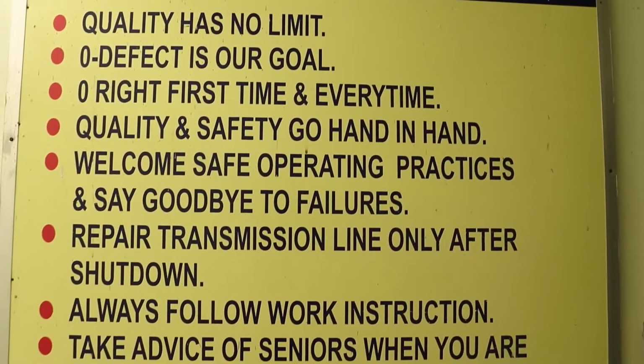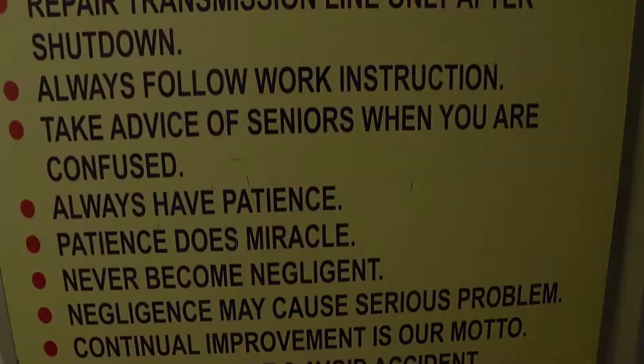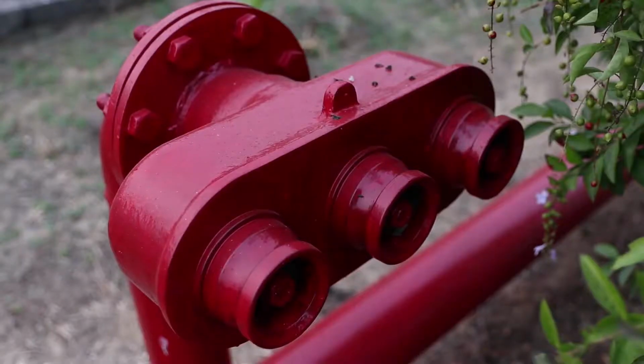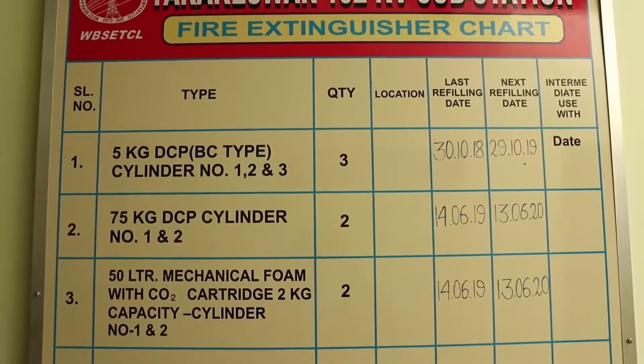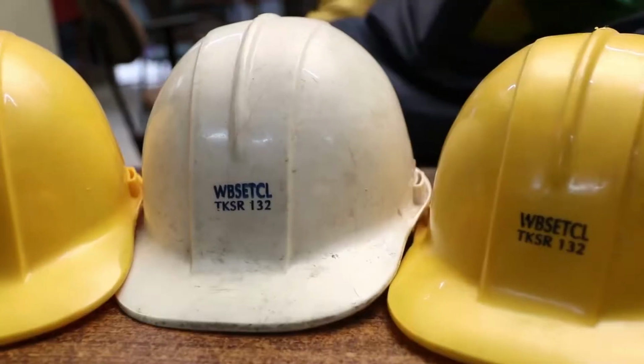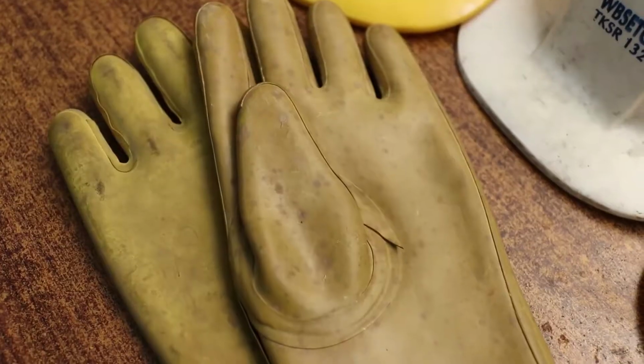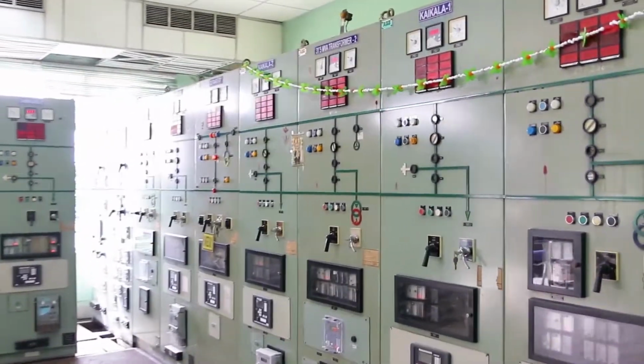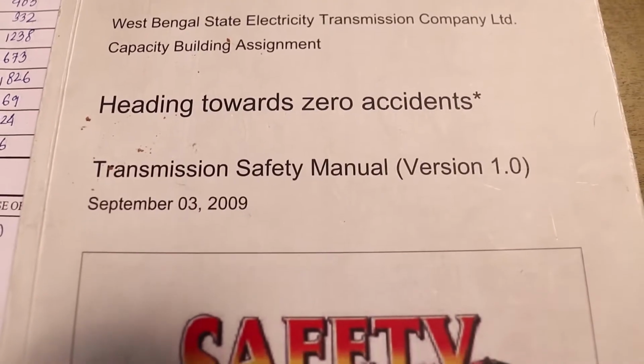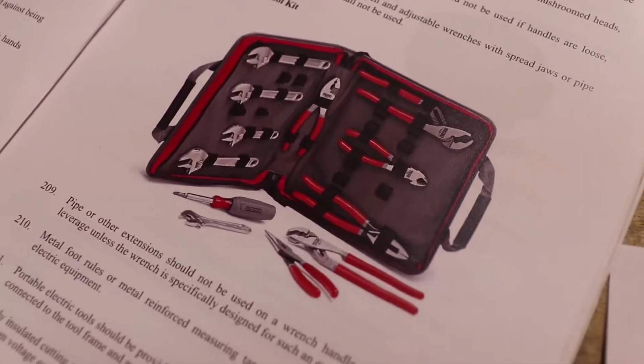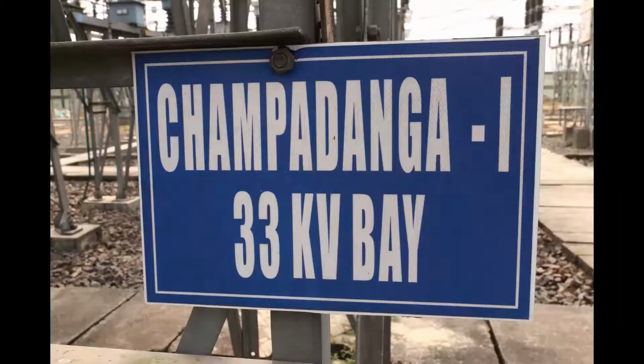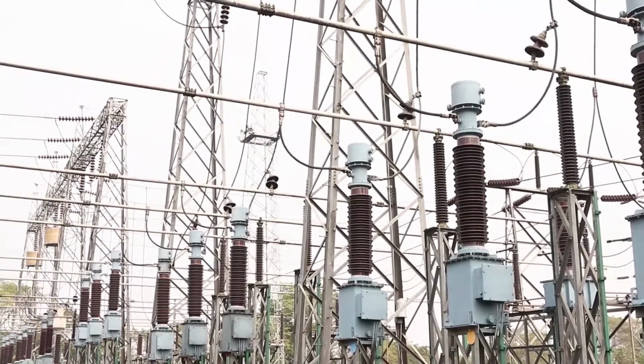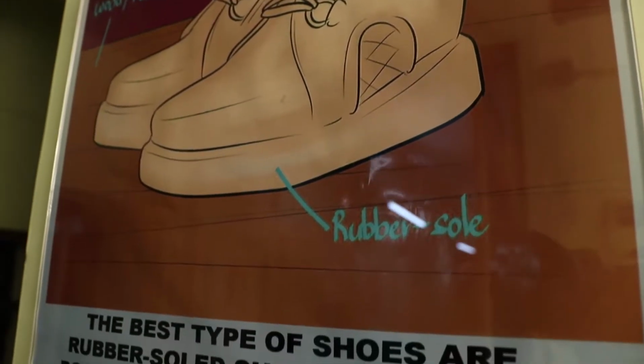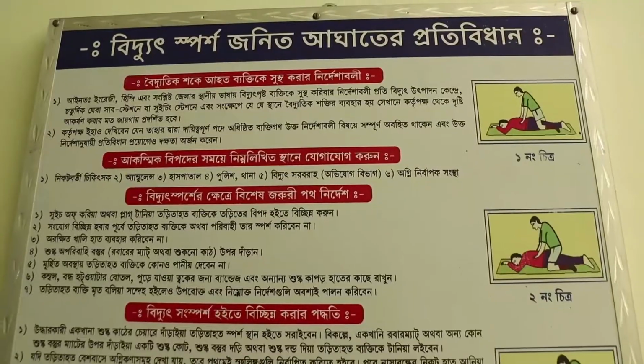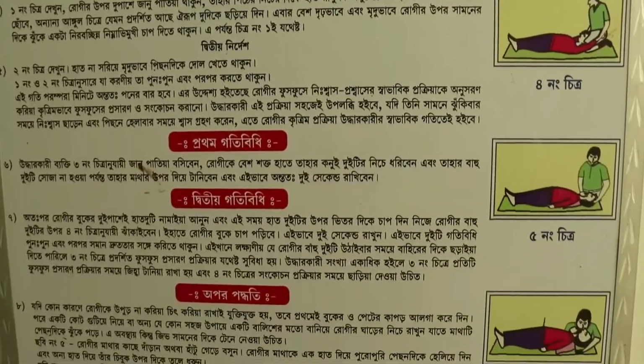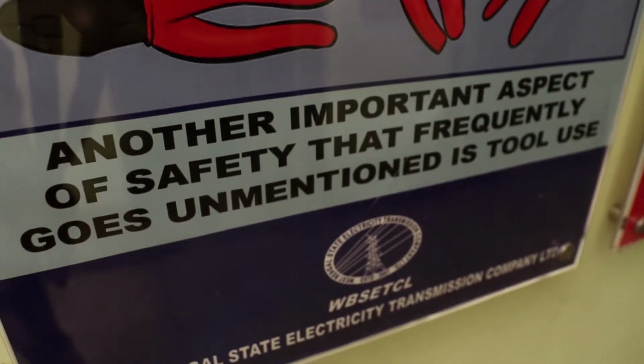Safety. Safety is one of the most important parameters at the site. Sufficient arrangements of different fire extinguishers and sand buckets are strategically located at the site. PPEs like safety helmets, safety belts, hand gloves and first aid boxes are readily available at the control room and maintenance. SOPs, switching instructions, safety and maintenance manuals are available in the control room. Bay markings and phase markings are properly done in the switchyard. Various safety posters are also placed in the control room for general safety awareness. Besides this, safety awareness programs are conducted at site from time to time.